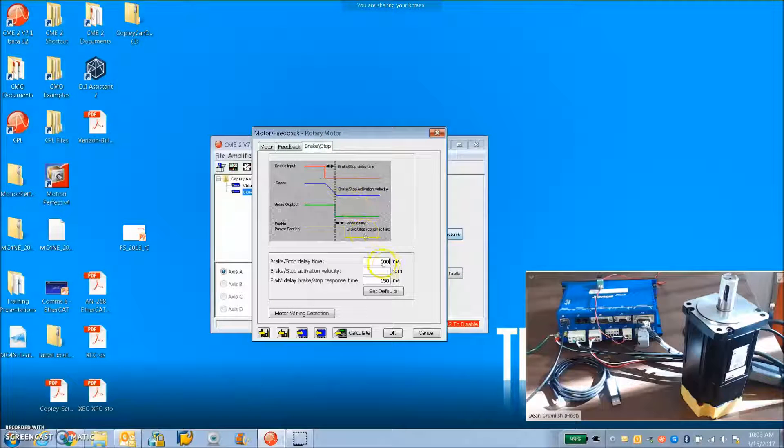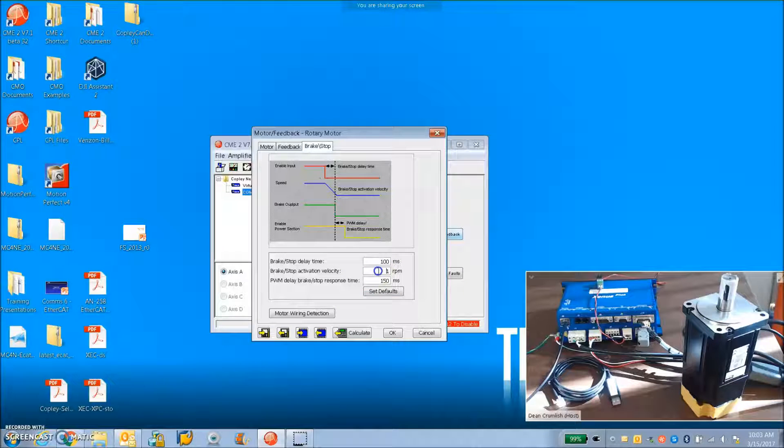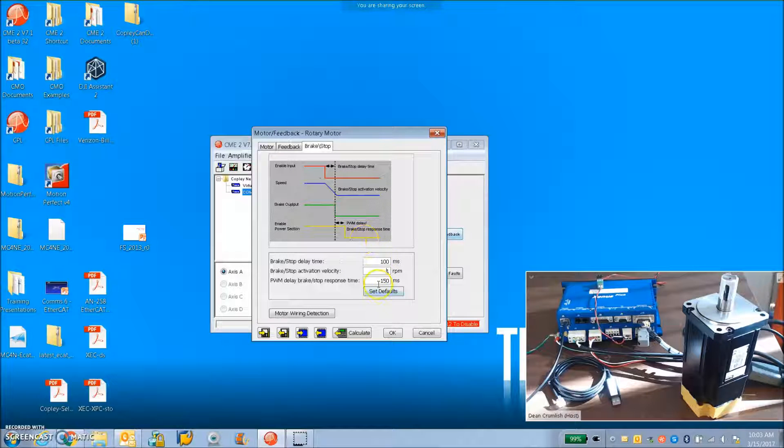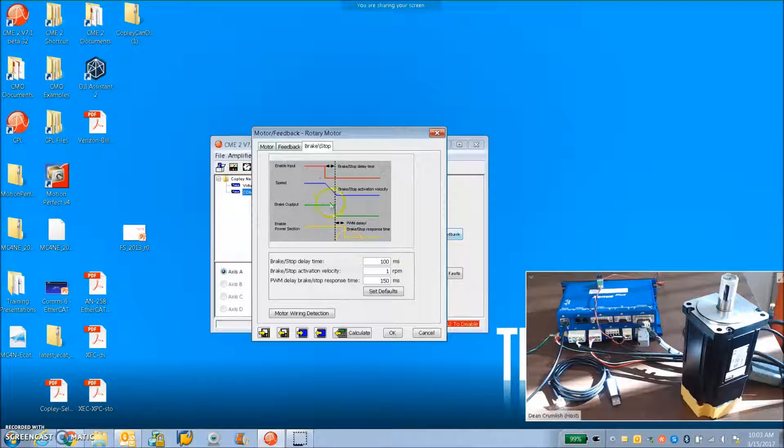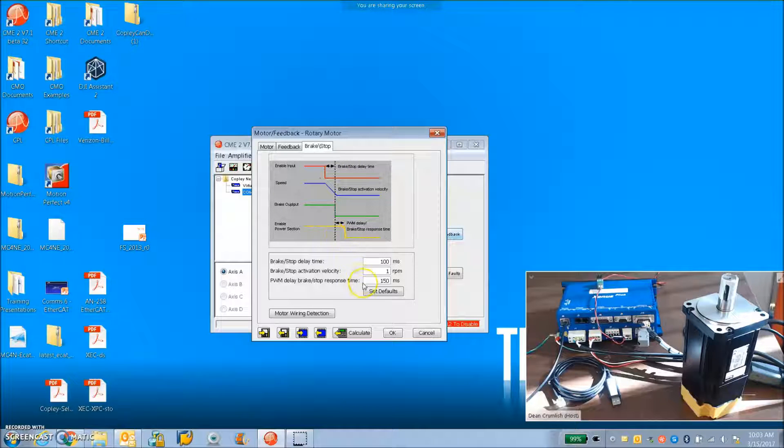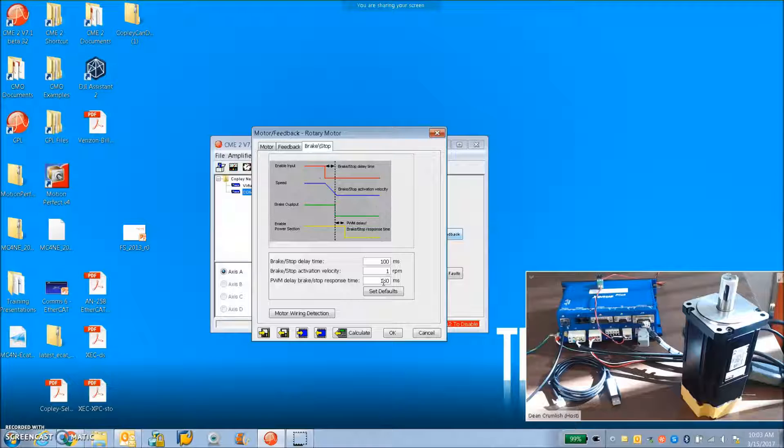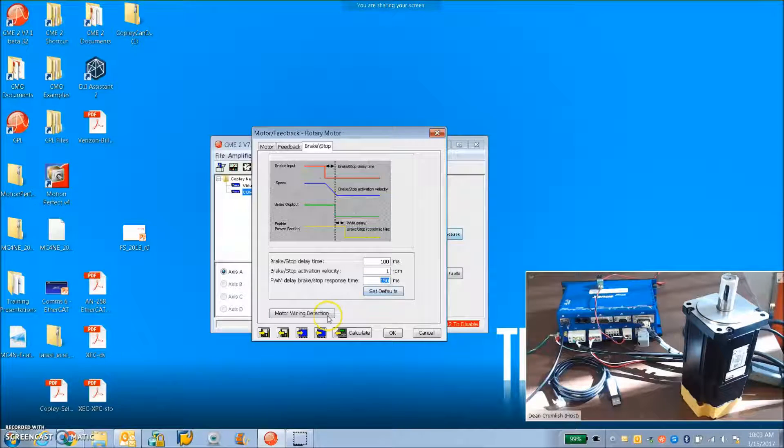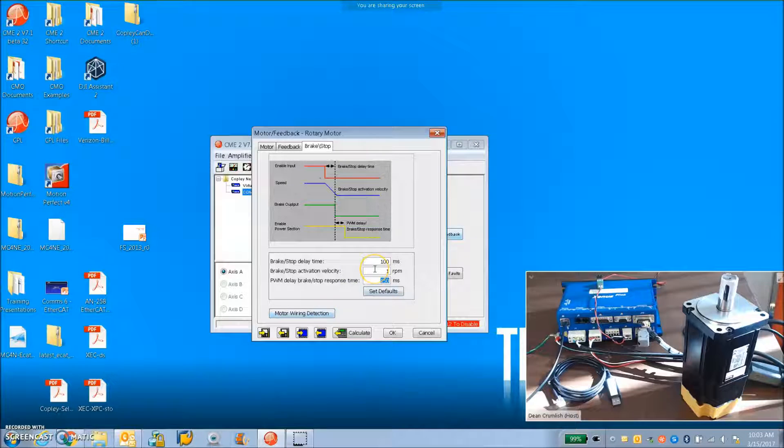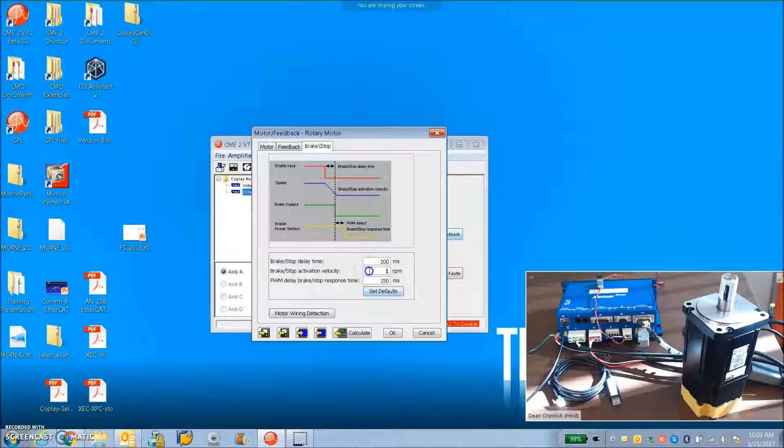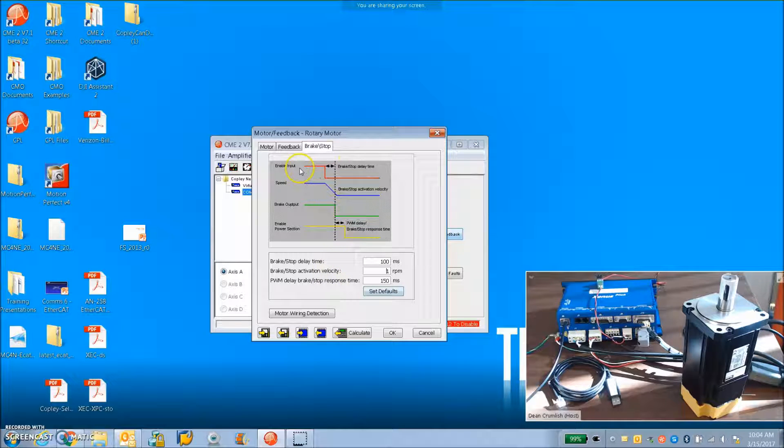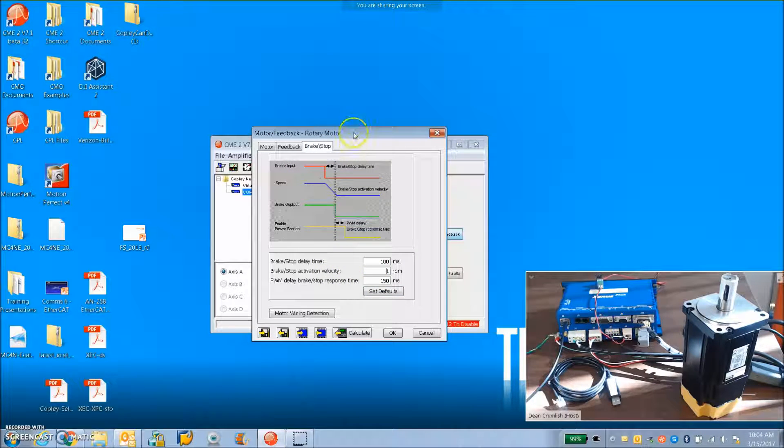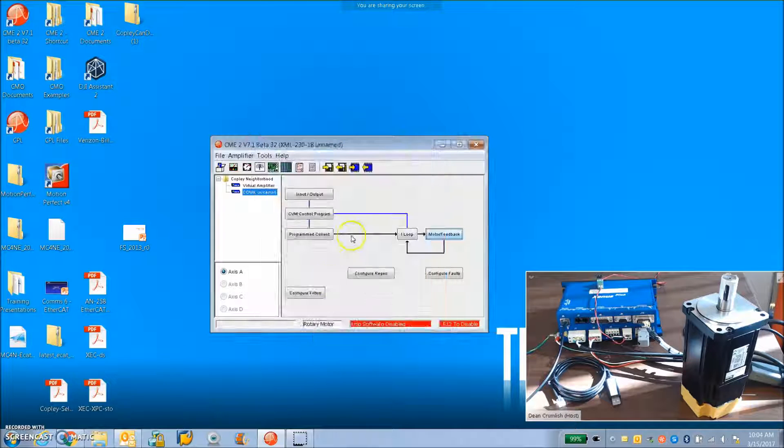One more thing I should mention is because this motor has a brake, we want to give it some time to stop before we turn the brake on. There's a safe speed at which we can turn the brake on. One RPM seems sufficiently slow. And the idea is we toggle the output to turn the brake on. It's a mechanical brake, it's a solenoid. It takes some time for the mechanical solenoid to kick in. We're going to give it 150 milliseconds of waiting for the brake to hold before we disable and let go. That way we can hold against gravity and nothing drops. This is the brake stop tab. It could be used for if you didn't have a brake, coming to a controlled stop and holding before you disable the output stage. That's really handy with a stow.